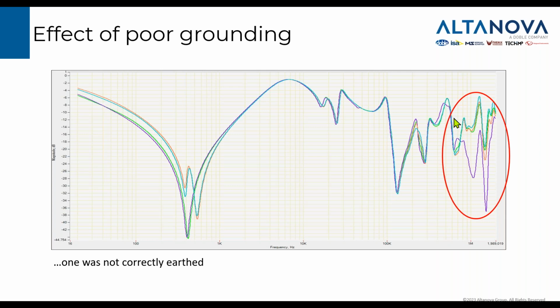One was not correctly earthed, and this purple line here, this was my measurement which I did on one of the phases, where I connected my measurement lead to the terminal for the measurement, but that lead also has a grounding connection. That grounding needs to be connected somewhere close to the bushing, to the good earth, and I apparently connected to that braid because it looked solid and proper, good for earthing, and I got this response much different than others. And I searched for the reason for that, and finally I found the reason. It was actually that earthing.